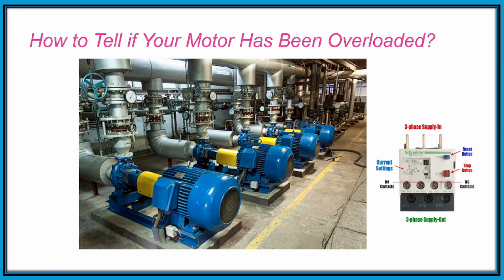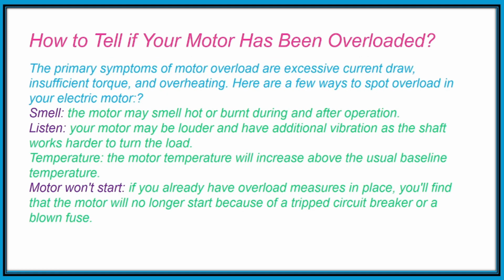How to tell if your motor has been overloaded? The primary symptoms of motor overload are excessive current draw, insufficient torque, and overheating. Here are a few ways to spot overload in your electric motor. Smell: the motor may smell hot or burned during or after operation. Listen: your motor may be louder and have additional vibration as the shaft works harder against the load. Temperature: the motor temperature will increase above the usual baseline temperature. Motor won't start: if you already have overload measures in place, you'll find that your motor will no longer start because of a tripped circuit breaker or a blown fuse.